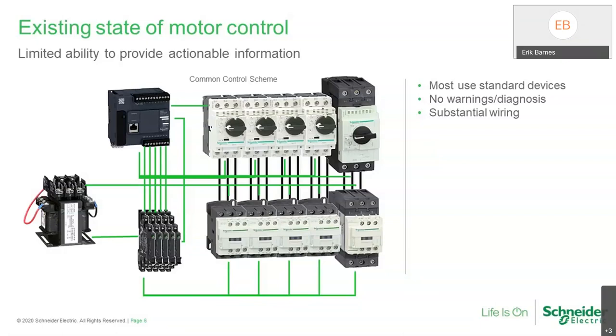Another key thing we notice is that, let's say we have a conveyor system or a pump, and there's an overload condition taking place. Nothing really changes from the control perspective until it gets to a tripping point. Then the overload protective device will trip, and that triggers the contactor to turn off the motor, and the conveyor or the pump stops. And then what happens? Your technician or operator is trying to figure out why the equipment stopped.